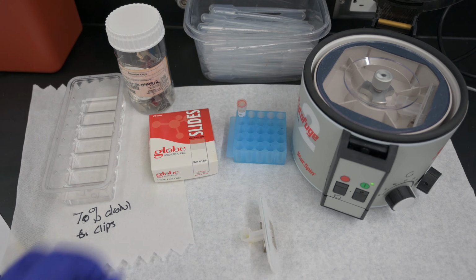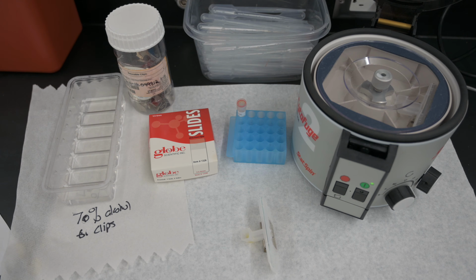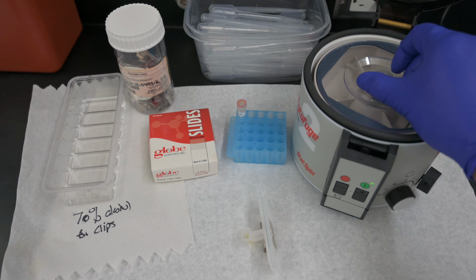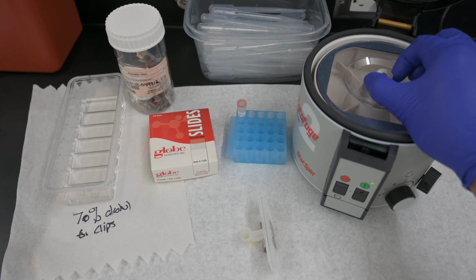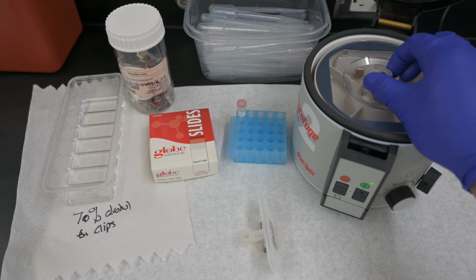Now it's important to keep the concentrator assembly on an angle here so that the fluid doesn't come into contact with the filter paper and the glass slide just yet. By placing it on the table on an angle, that prevents the fluid from moving any further into the concentrator assembly. So next we're going to add the concentrator assembly loaded with our sample into the cytocentrifuge.